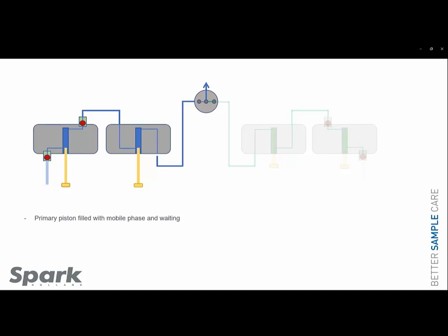We will go a little bit deeper into the technology. As you can see, the primary piston filled the mobile phase into the primary pump head and it's waiting. The mobile phase is colored dark blue. The pressure inside the primary pump head is 6 bar below the system pressure. The system pressure is at the secondary pump head, as well as on the purge valve. The reason why the primary pump head is 6 bar below the system pressure is because we want to ensure that the outlet check valve is closed at all times.